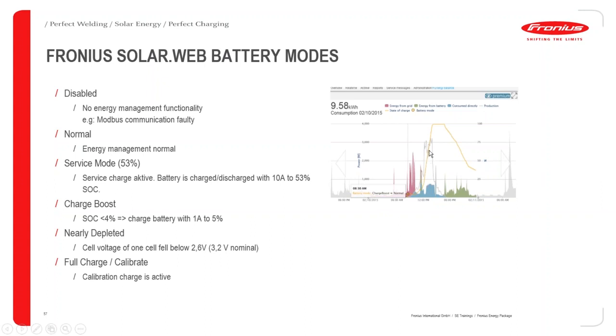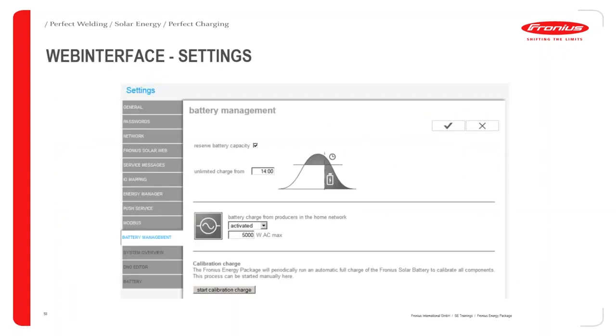Then you've got the service mode. If that comes up, it'll actually show you on there and whereabouts that is. Charge boost is if the state of charge gets so low because it never gets charged, something like that could happen in winter in Europe, then it will charge it up to 5% to make sure it stays at a decent level there. Then you've got nearly depleted, which is more of a service thing which would come through, and then calibrate as well. You'll see when a calibration charge takes place when it actually happens in there.